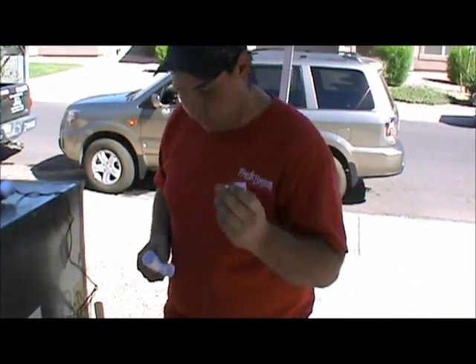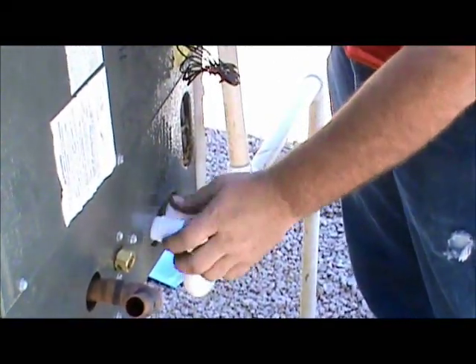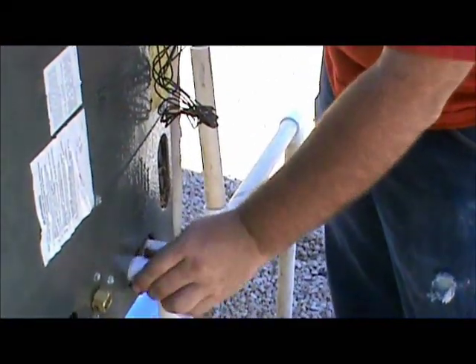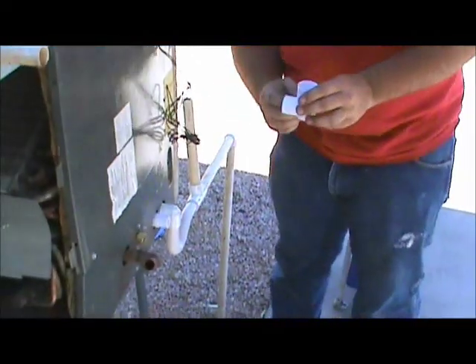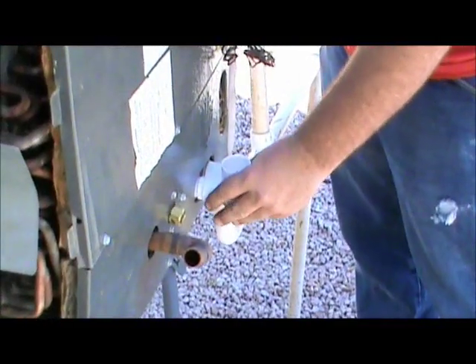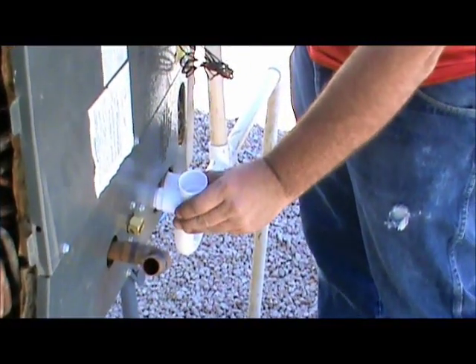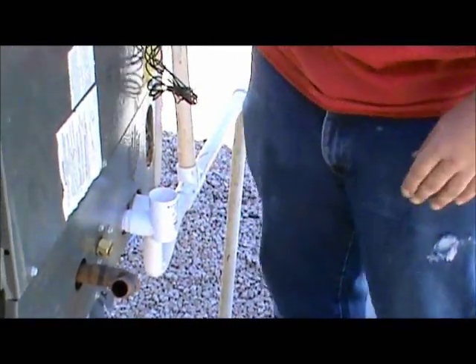First thing you want to do is take your nipple and put it right here inside your unit. Then you're going to take a little glue and put glue on here and stick your T on here like that. Make sure you glue it, because otherwise when the unit runs it can vibrate and it'll turn off the unit and you'll get to crawl back in your attic. So make sure you glue that right there.